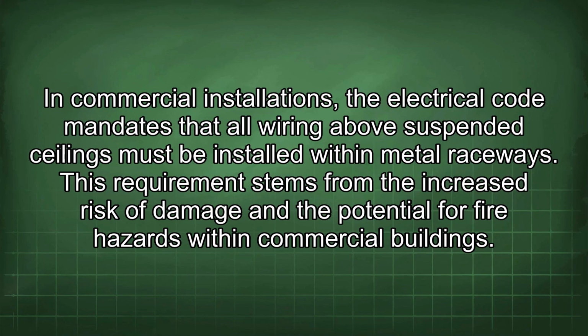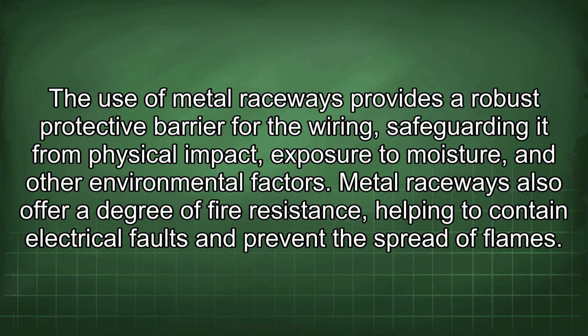In commercial installations, the electrical code mandates that all wiring above suspended ceilings must be installed within metal raceways. This requirement stems from the increased risk of damage and the potential for fire hazards within commercial buildings. The use of metal raceways provides a robust protective barrier for the wiring, safeguarding it from physical impact, exposure to moisture, and other environmental factors. Metal raceways also offer a degree of fire resistance, helping to contain electrical faults and prevent the spread of flames.